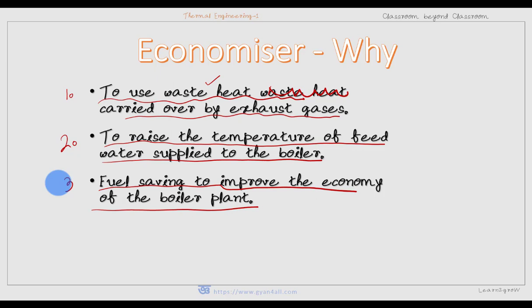We can say an economizer is a device in which the waste heat of the flue gases is utilized for heating the feed water — to recover some of the heat being carried over by exhaust gases and use it to raise the temperature of feed water supplied to the boiler. As a result, fuel saving is possible, which improves the economy of the boiler plant. That is why it is called an economizer.